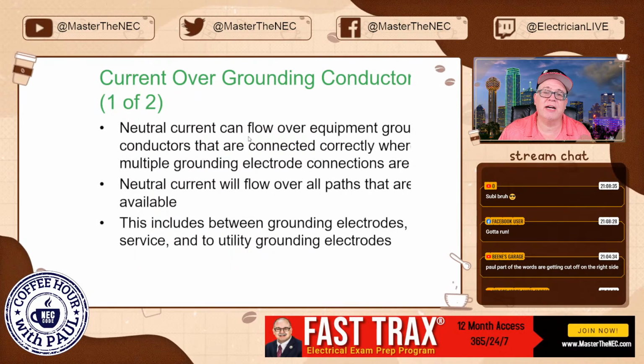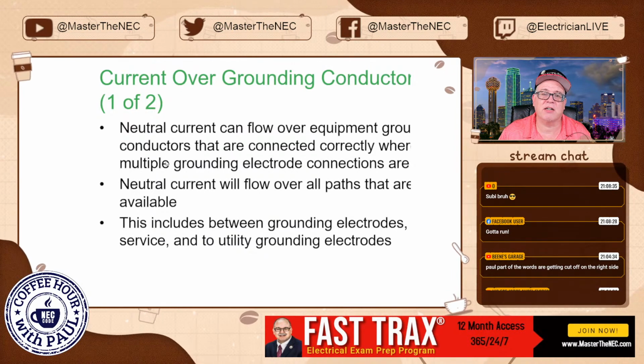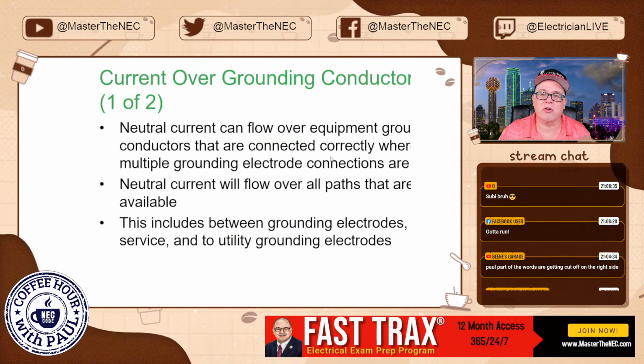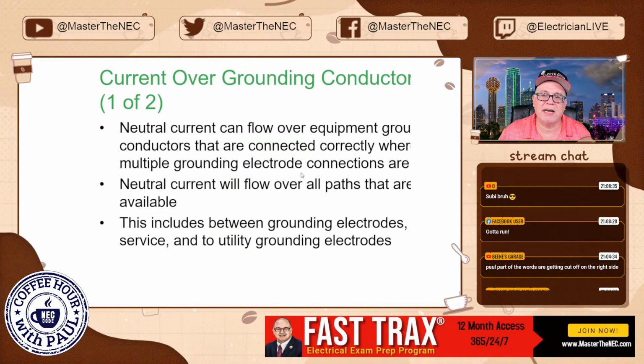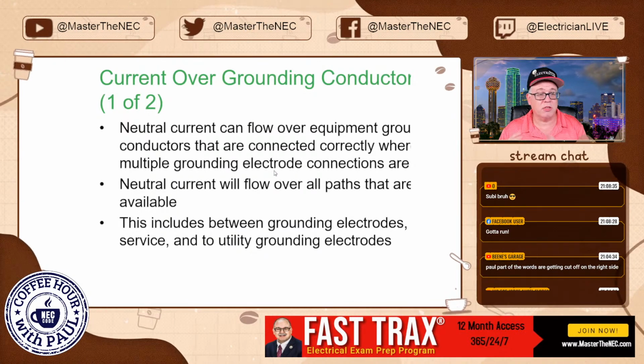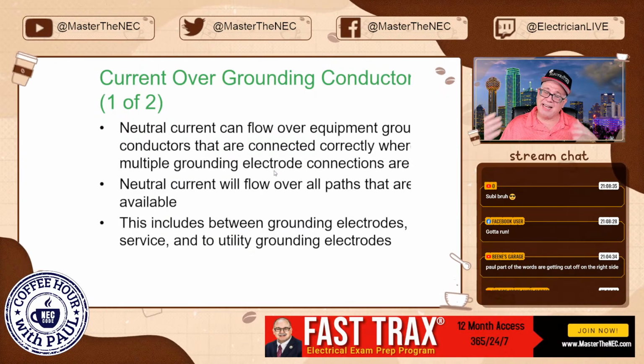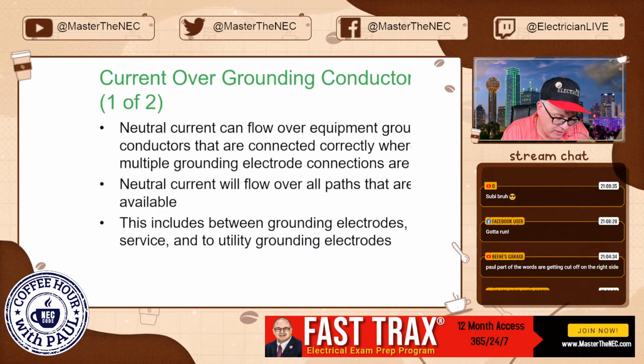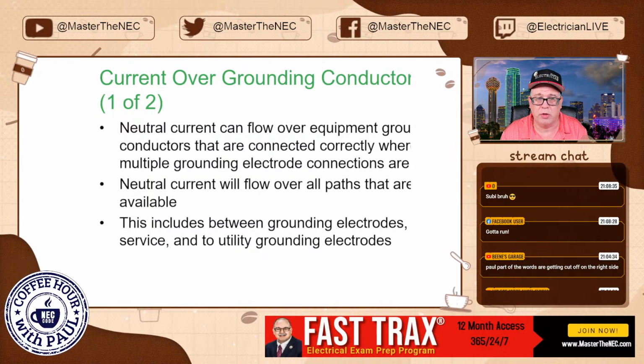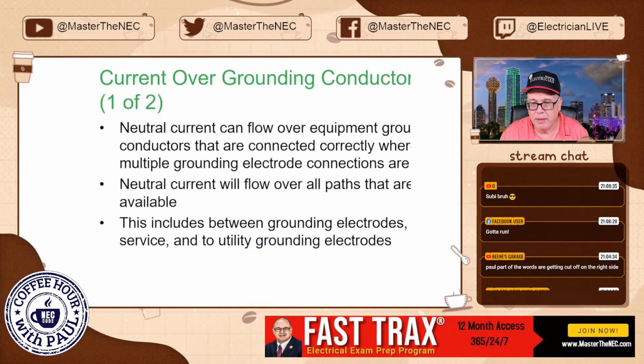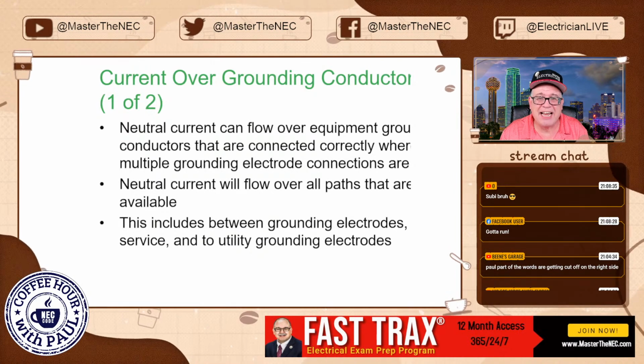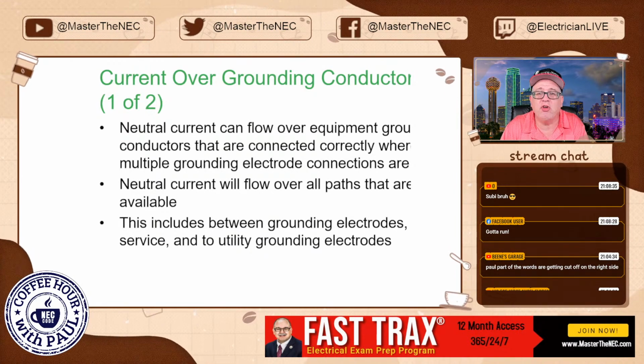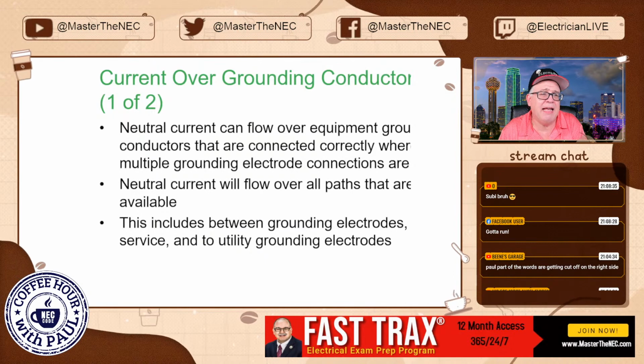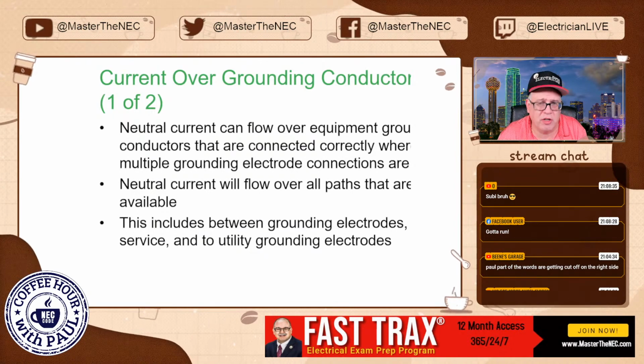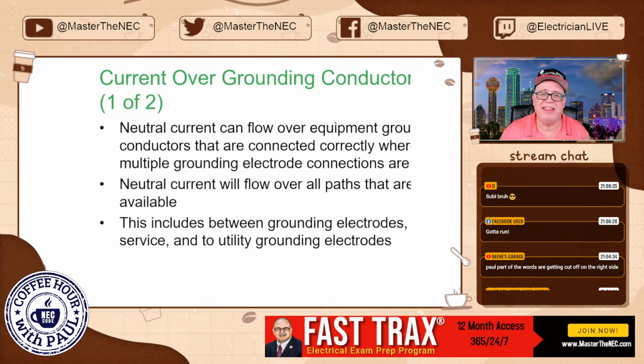Now, neutral current can flow over equipment grounding conductors that are connected correctly, where multiple grounding electrode connections are made. So look, you can even make connections downstream. And this is why Code Panel 5 struggled with defining objectionable current, because there are some connections that will allow you to impose objectionable currents. And we had to struggle with that.